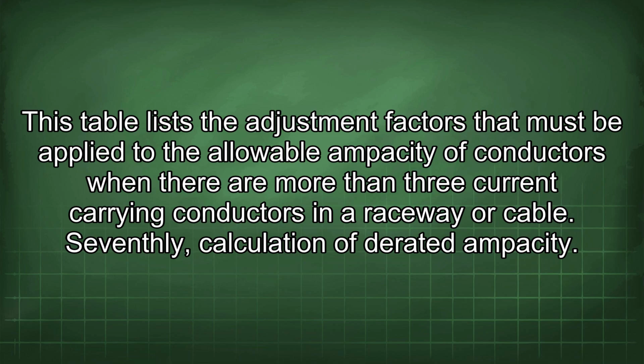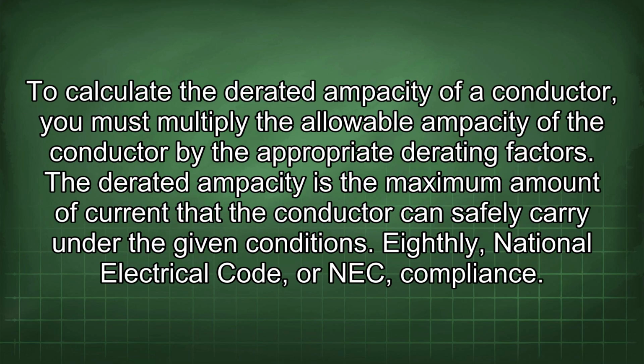Seventhly, calculation of derated ampacity. To calculate the derated ampacity of a conductor, you must multiply the allowable ampacity of the conductor by the appropriate derating factors. A derated ampacity is the maximum amount of current that the conductor can safely carry under the given conditions. Eighthly, National Electrical Code, or NEC, compliance.